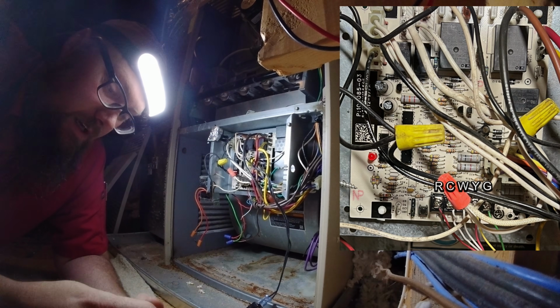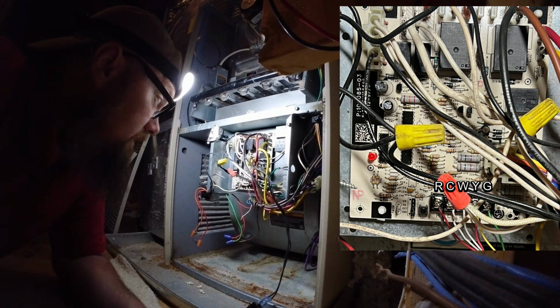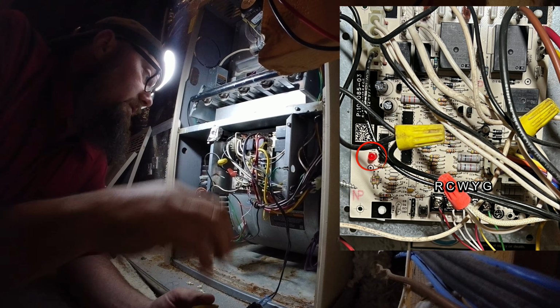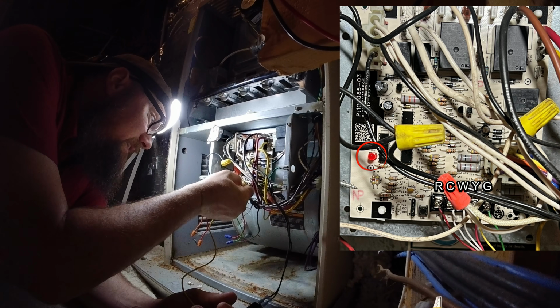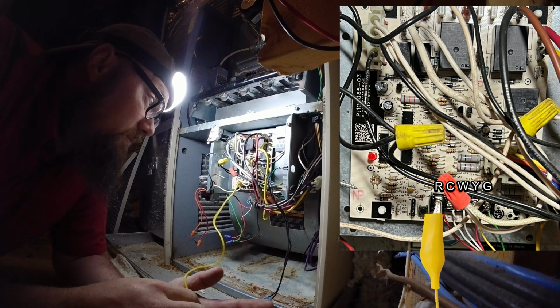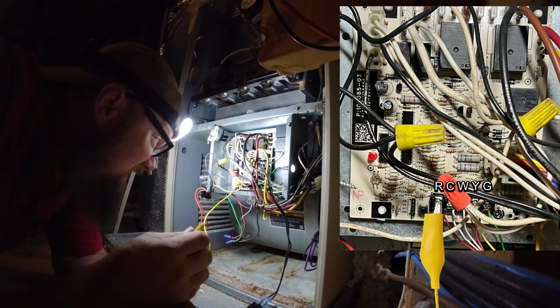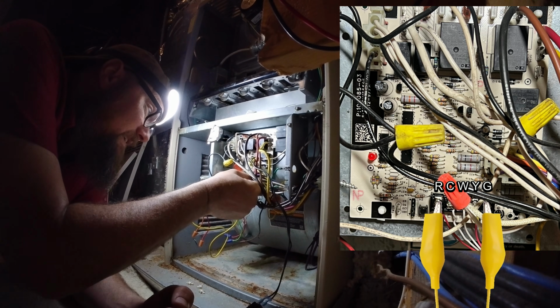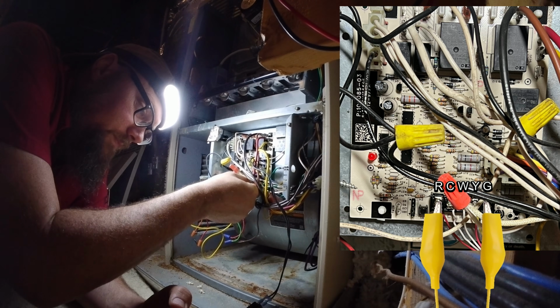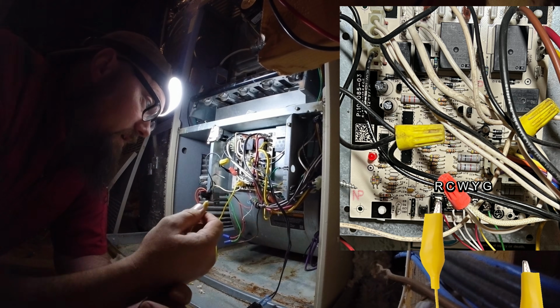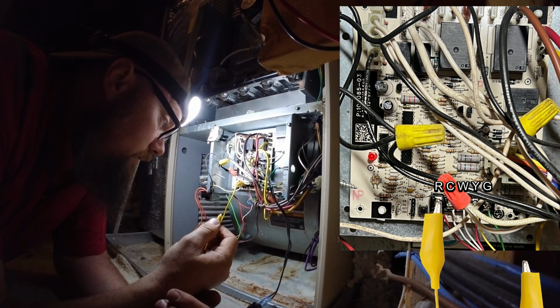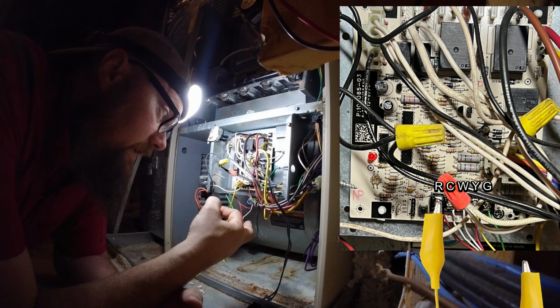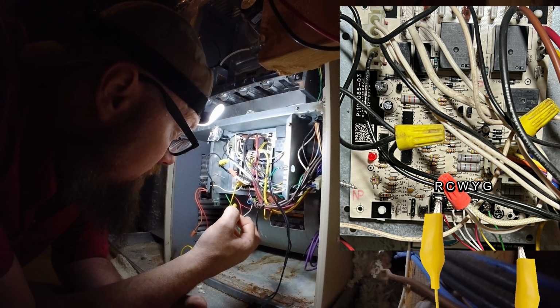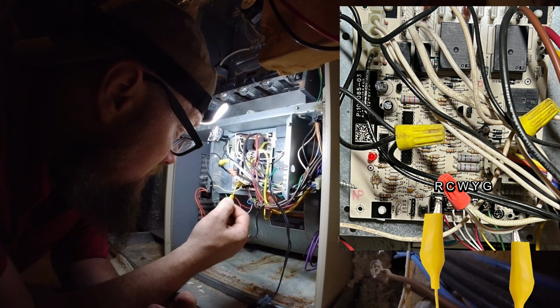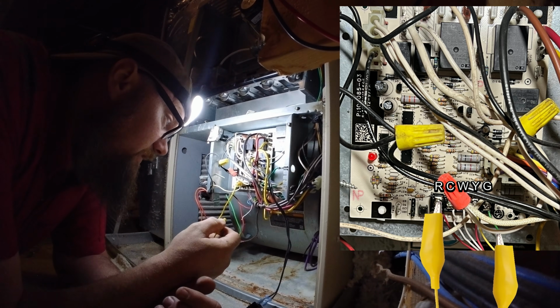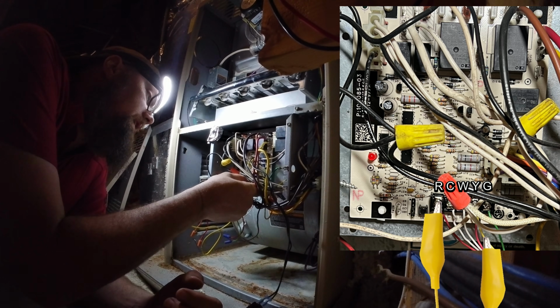So we just disconnected the outdoor unit so we can check it individually. So we have our LED light going. Check between 24 volt hot and green. So the fan does come on. Don't have an issue there. We'll check between 24 volt hot and, see that yellow wire should go to the system and then back to the zone board. So we'll check it.